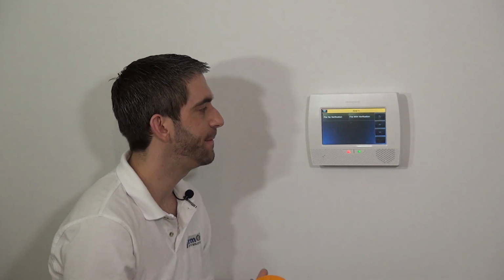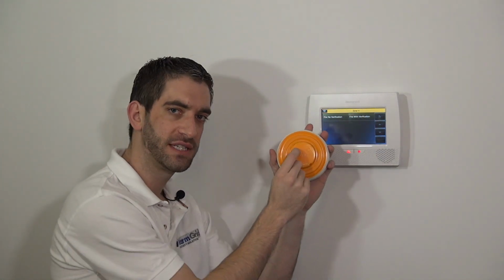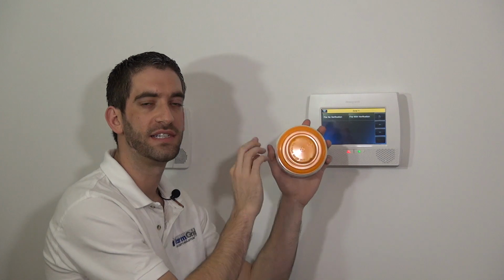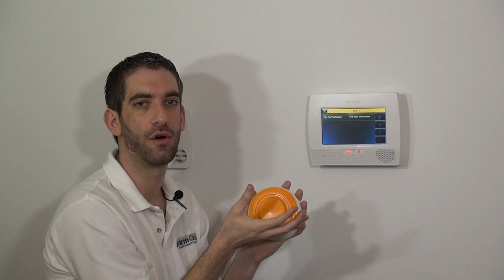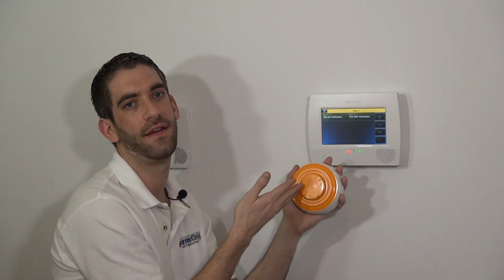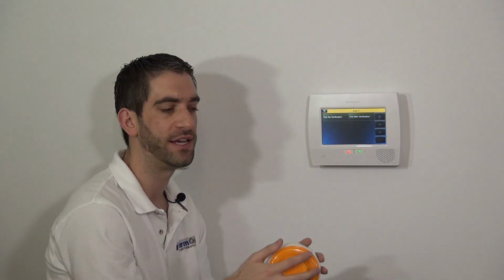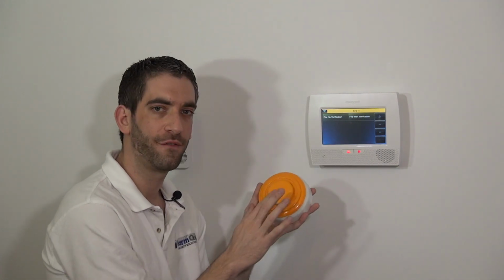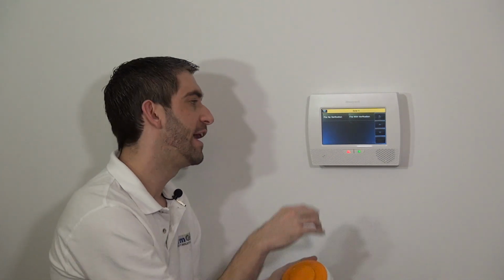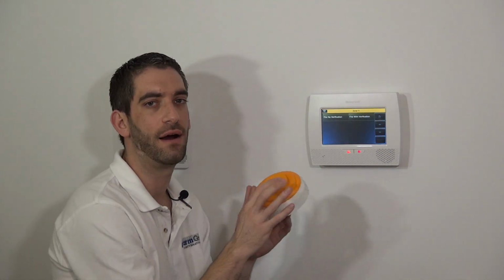And the way it verifies it, if you did with verification, the very first time that this sensor detects smoke, it would sound the alarm, but then cut it off right away. So basically it sees the trip, but it restores itself automatically. And then if it triggers again, then it would cause the alarm. So if it was a slight false alarm, smoke got in there because you're cooking, or someone was smoking, something where it's not a true fire situation, the verification would ignore the first trip and it would only send the alarm to the central if it was triggered again after it ignored the first trip.